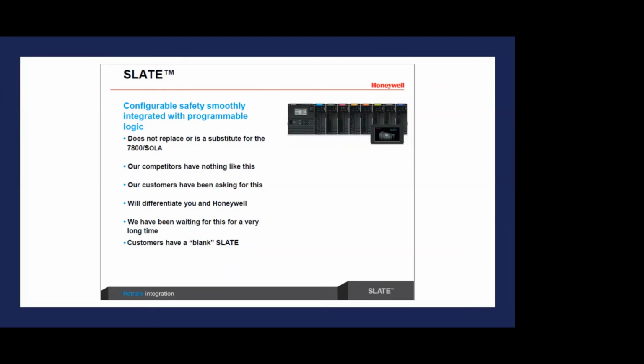PLC to tie in with the combustion system. They're still going to have to bring in a limit control. They're still going to have to bring in some form of annunciation. So all different hardware, all different wiring, all different platforms that all have to be programmed a different way. That's where the differentiator really is: one platform for programming, reducing the wiring, time and labor.